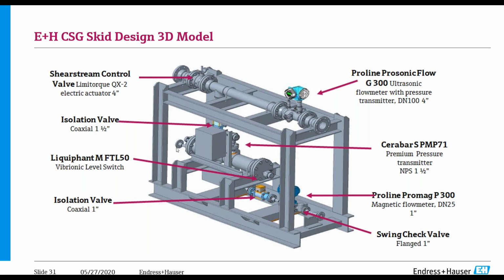The other key point on the design of the Endress+Hauser inline separator is that we actually do level control inside the separator. Now this is key. We have seen a number of designs in the field where there is no level control inside the inline separator. Endress+Hauser believes from our CFD modeling that in order to achieve maximum separation inside the separator, you need to have control of the level itself. So what typically happens inside the separator is, you can see there are two level switches there, the Liquiphant FTL50s. So there's a low level switch and a high level switch. And those level switches will be monitoring the water level inside the separator. And the primary role of those level switches is to switch isolation valves.